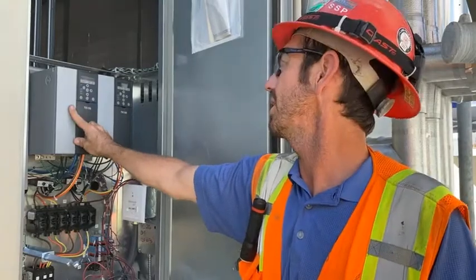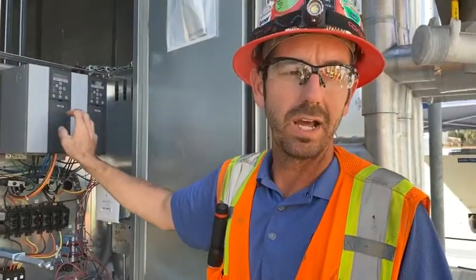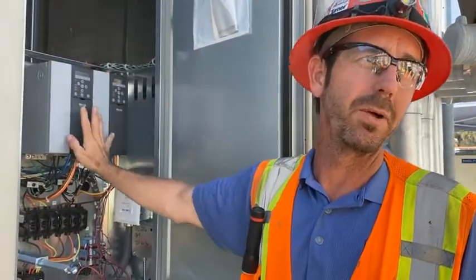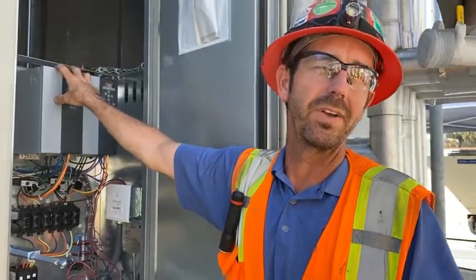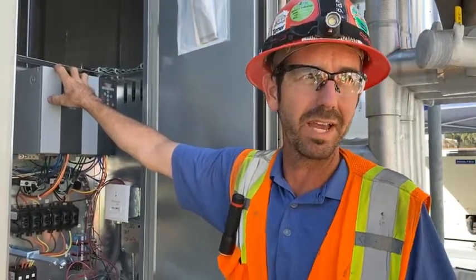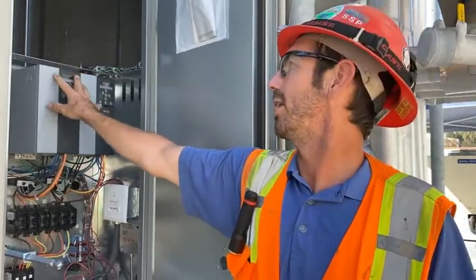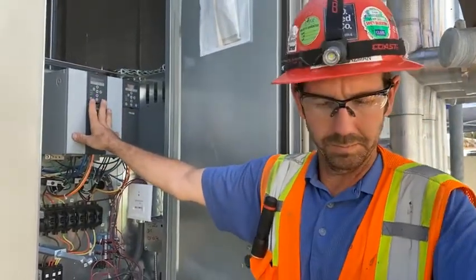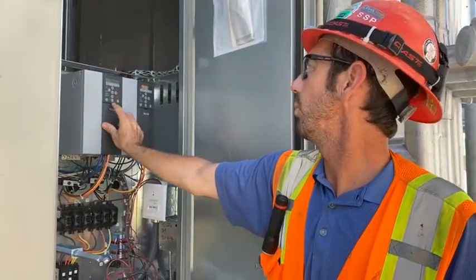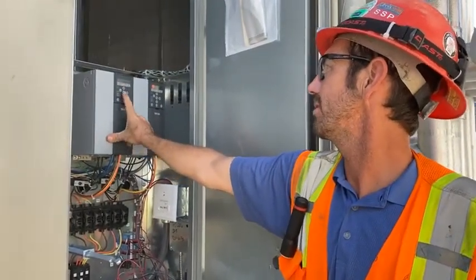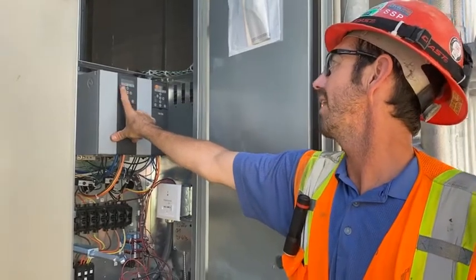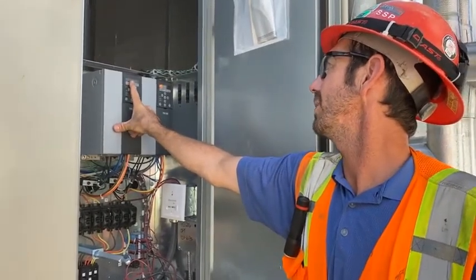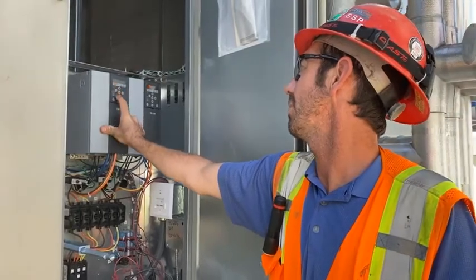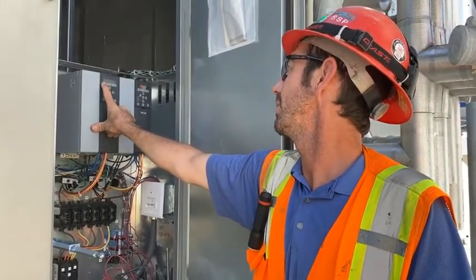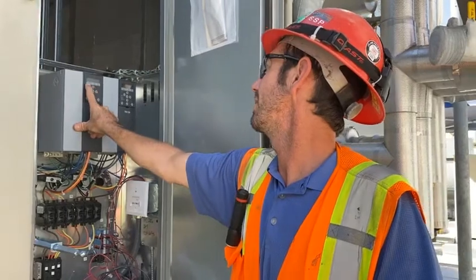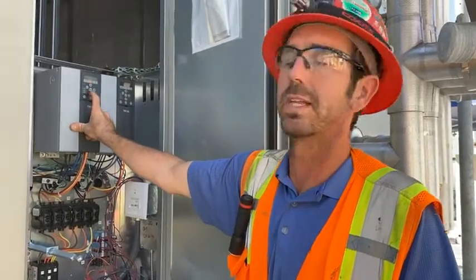Okay, so when you make a change and you want to upload that information into the keypad, remember uploading is taking it into the keypad out of the drive. When you download it, it takes it from the keypad and puts it back in the drive. So when you have a drive failure, you'll want to download a full set. The drive has to be off to do this, so we're in off mode. We do copy save. 0-50 is the LCP copy. Right now it says 0, no copy. We press OK. It lights up with a black arrow. And we press up. And it says all to LCP. So all to the liquid crystal panel.